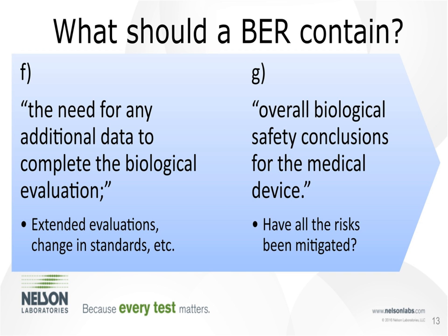Part F covers the need for any additional data to complete the biological evaluation — this is where you identify any gaps. This can happen with extended evaluations, changes in standards that occurred since the testing was performed, or when submission timing differs from when testing was done. Part G is the final conclusion: the overall biological safety conclusions for the medical device — have all the risks been mitigated, and can we say the device is safe?